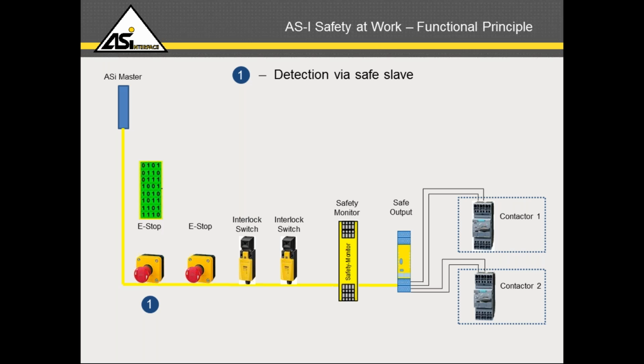And the ASi master polls all slaves on the network, including safe slaves, just as it does the standard slaves. And the safety slave responds a little differently than the standard slave does. It responds with this unique 32-bit code sequence. And that code sequence changes if the safety slave is activated, or if there's a fault, or obviously if there's a communication problem, then that code wouldn't get back to the safety monitor.